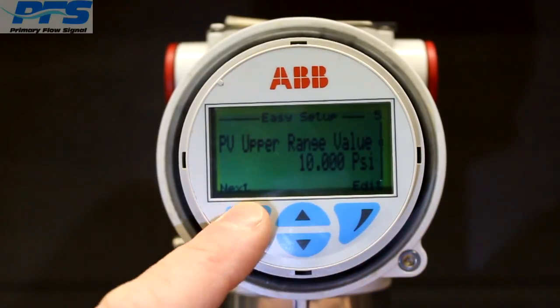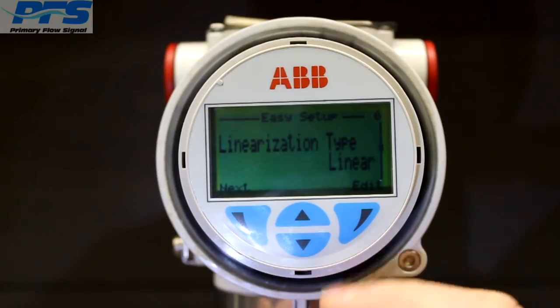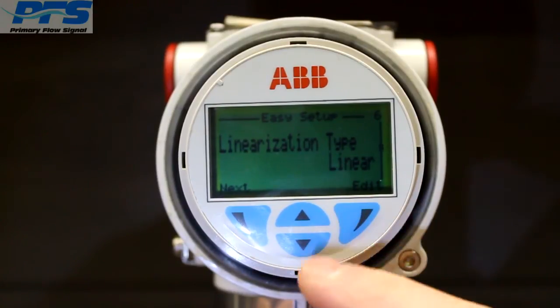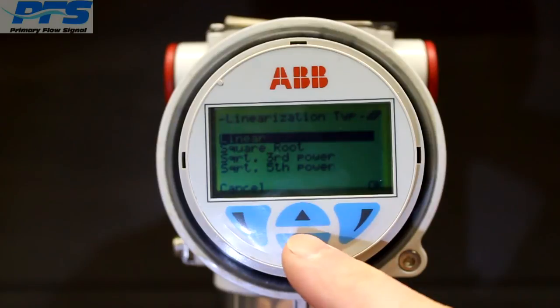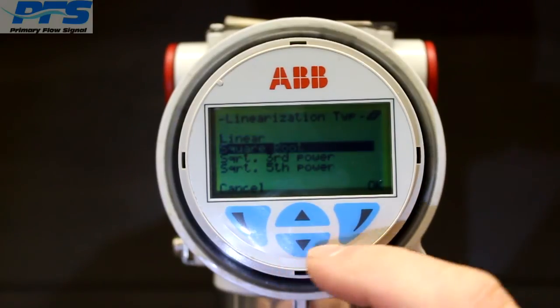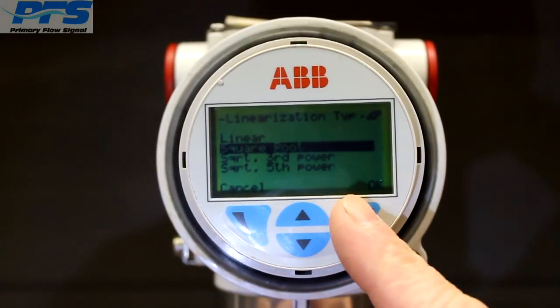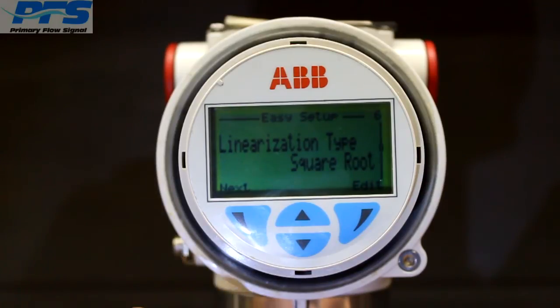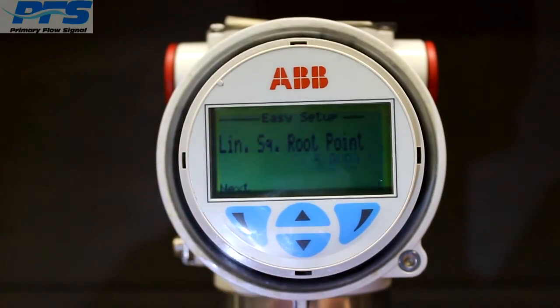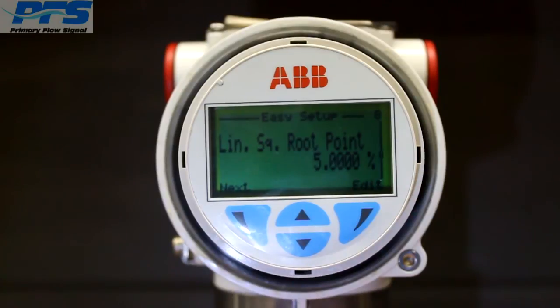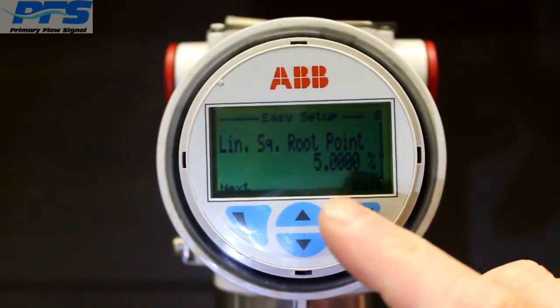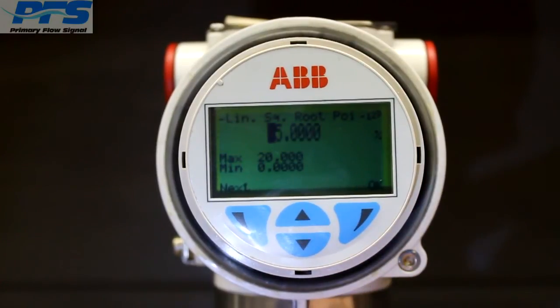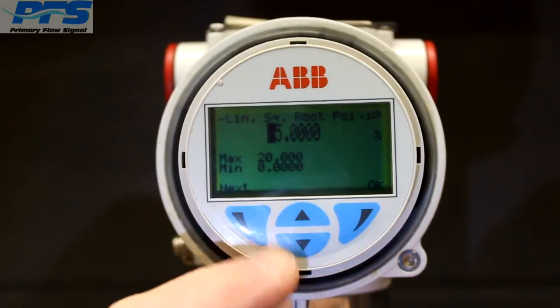Next one is linearization type. To change that, you hit edit again, and most of these functions are changed the same way. Then you've got linear, and I'll change it to square root and hit OK. Linearization type is now square root. We'll hit next again to the next function, the linear to square root transition point. If you want it on, you can turn it off, I believe. Right now it's at 5%. You can turn it down to 0%, or bring it up as high as 20%. We're not going to change that, so we'll hit OK.